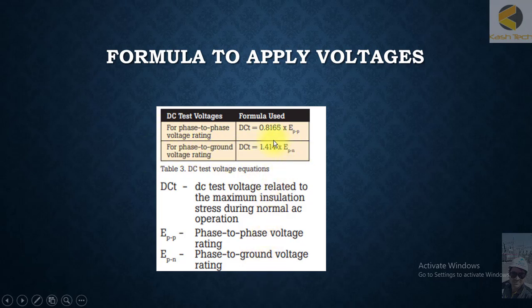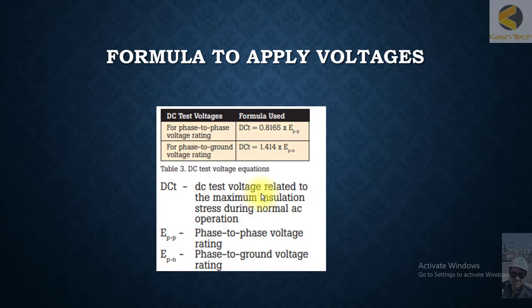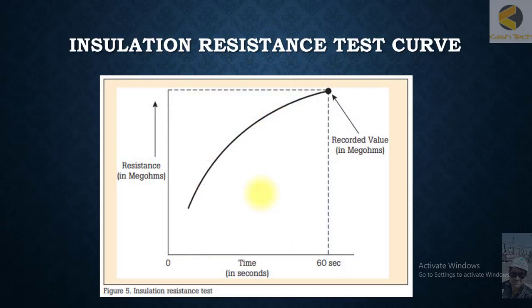For maintenance testing, the applied DC voltage level is less than the equipment rating. In contrast, for initial installation testing, if factory values are unknown, you apply two times the rating plus 1 kV, since this is the first-time test to determine whether the equipment passes or fails.